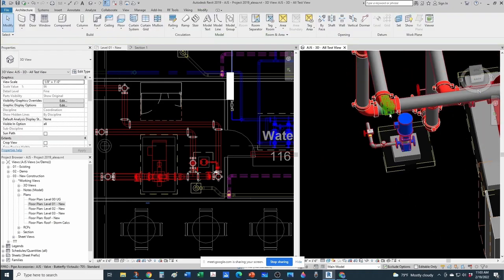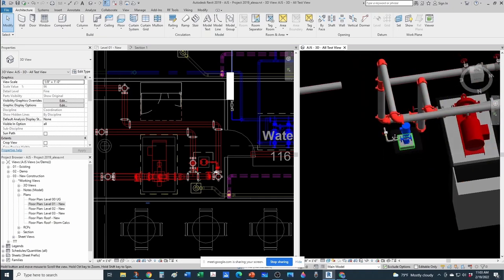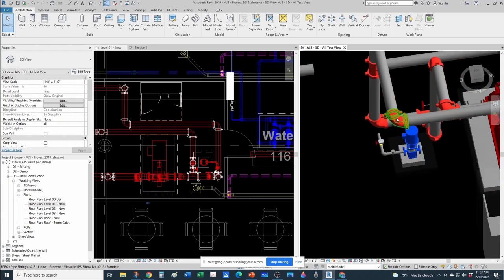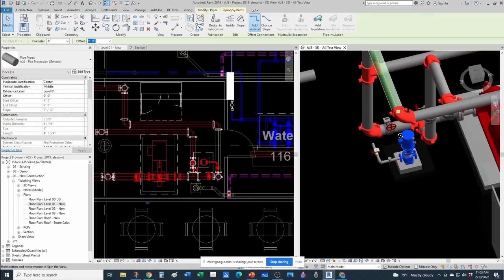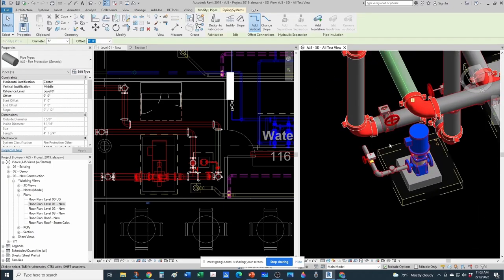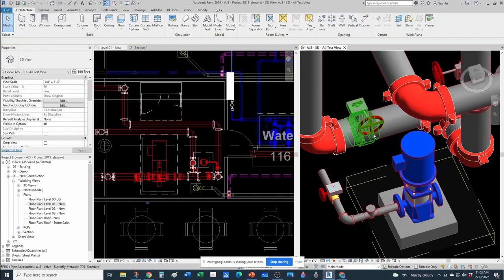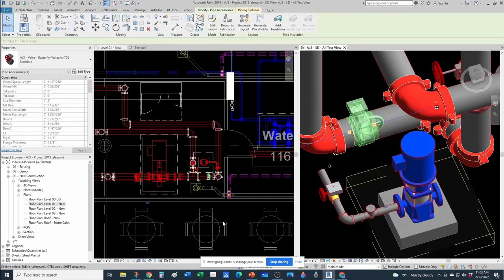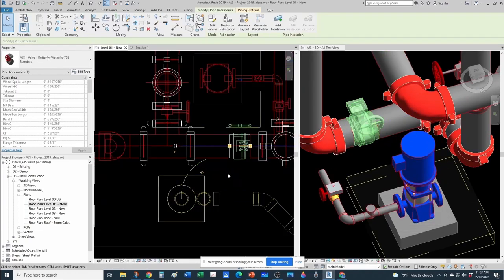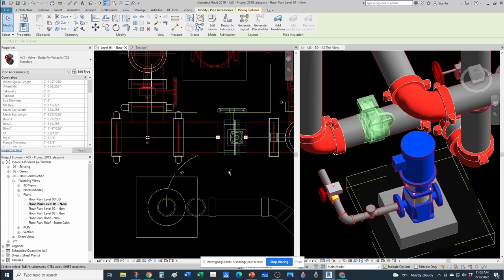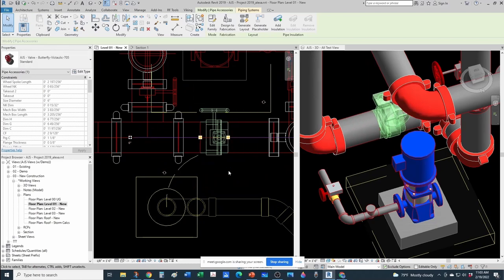And then that has to be tied into my discharge. So I'm pretty tight right there. That has to be after this isolation valve, so I don't have too much space. So what I'm gonna do is take this butterfly valve and take it as close as possible to my bypass.